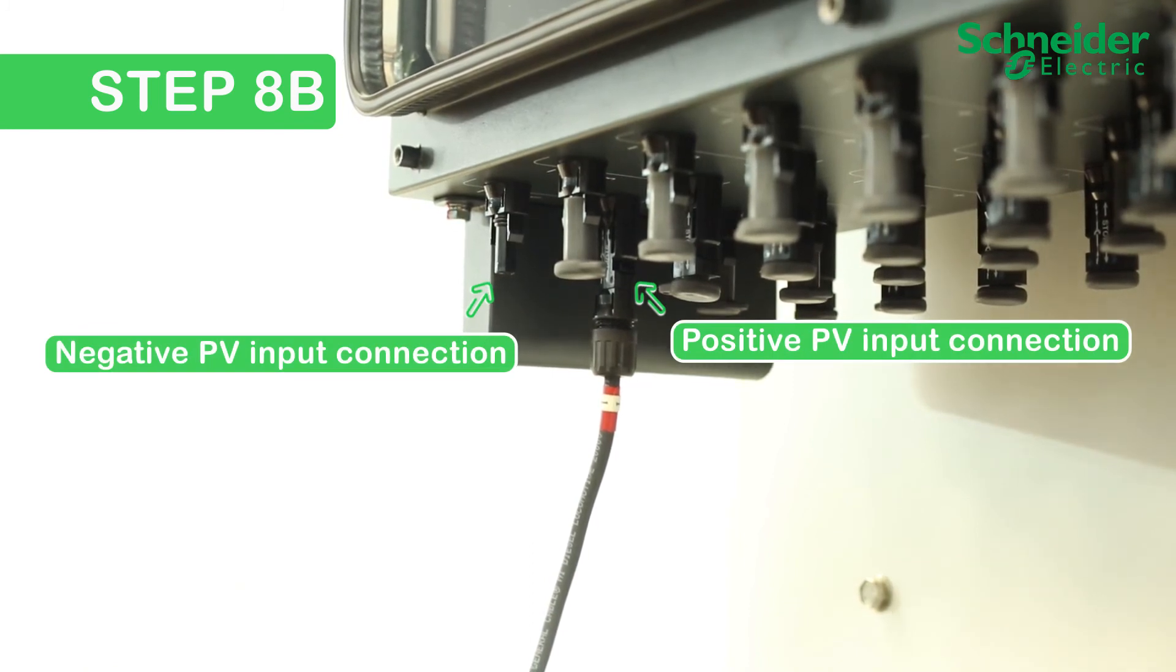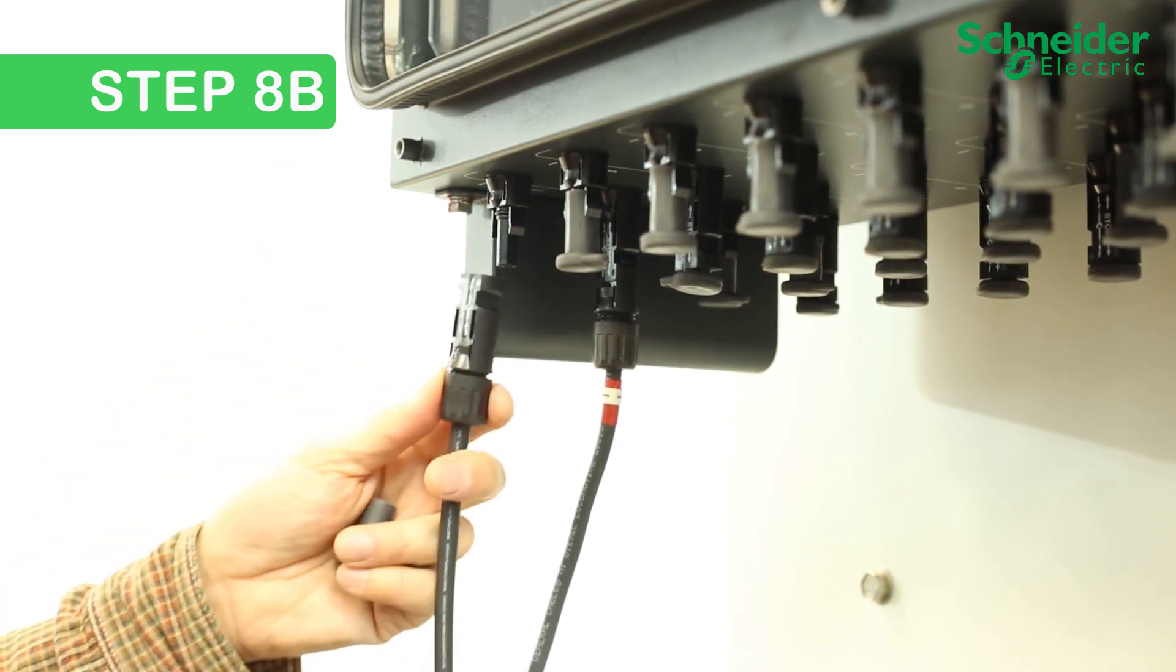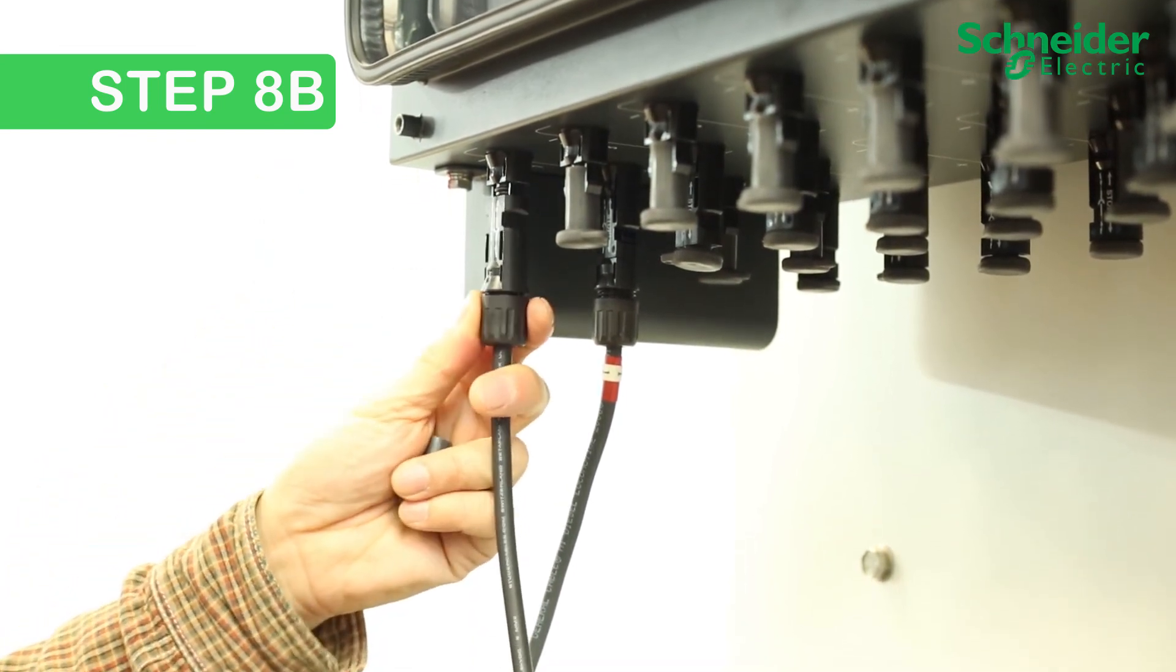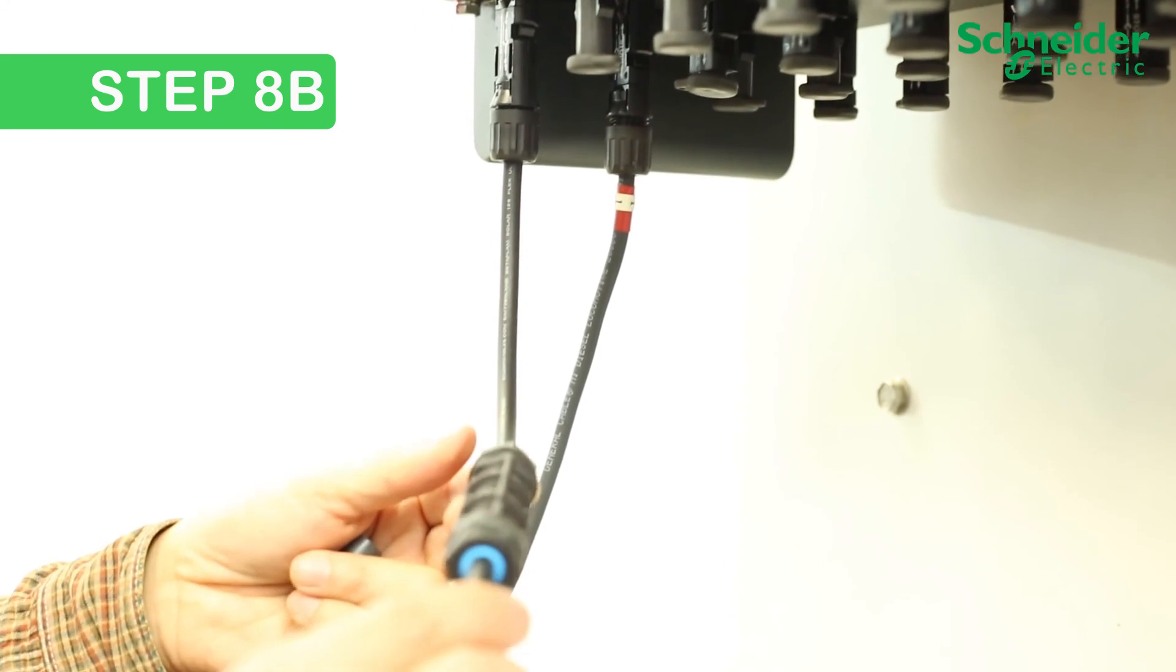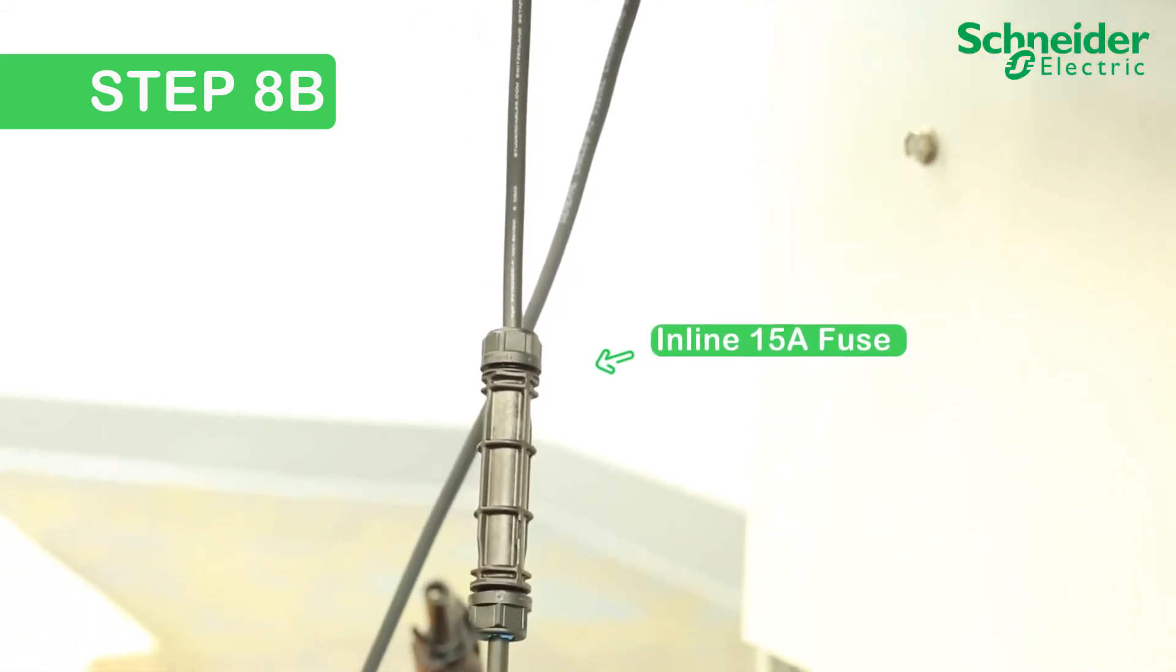Where circuit protection is required on the negative leg, add MC4 15-amp inline fuses to the negative inputs of the CL60E. Your PV string can then connect to the other end, or directly to the CL60E when negative fusing is not required.